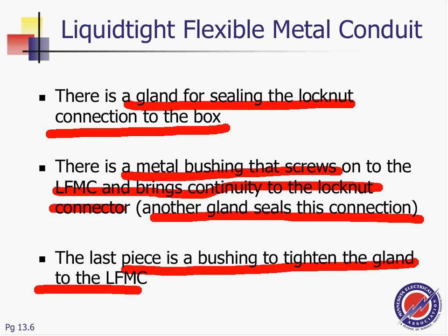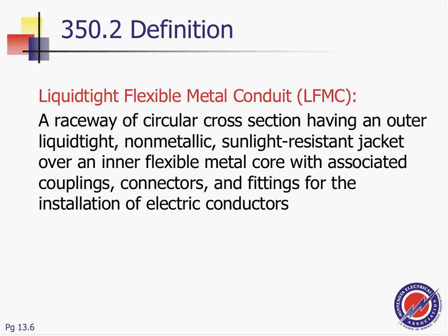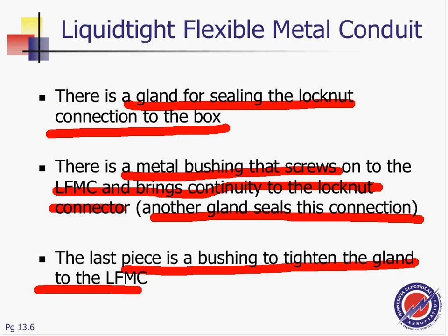And I'm sure I've seen it. We have a picture of that too, but those guys are sealing it. You do not want the water to seep into the conduit through the connector. So your connector is going to be a special type of connector with nuts and seals and so forth. Not any connector.